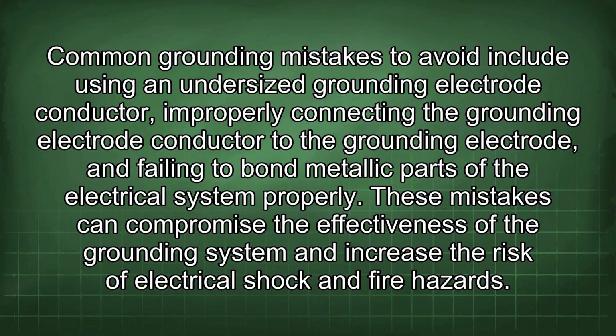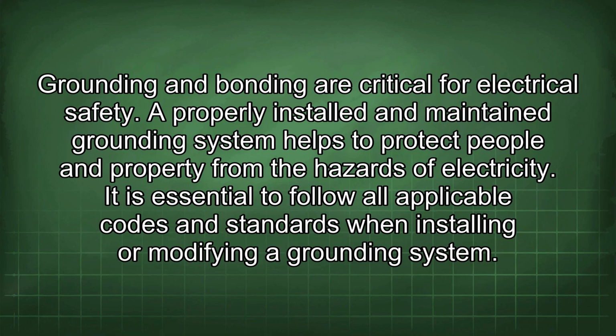Common grounding mistakes to avoid include using an undersized grounding electrode conductor, improperly connecting the grounding electrode conductor to the grounding electrode, and failing to bond metallic parts of the electrical system properly. These mistakes can compromise the effectiveness of the grounding system and increase the risk of electrical shock and fire hazards. Grounding and bonding are critical for electrical safety. A properly installed and maintained grounding system helps to protect people and property from the hazards of electricity.